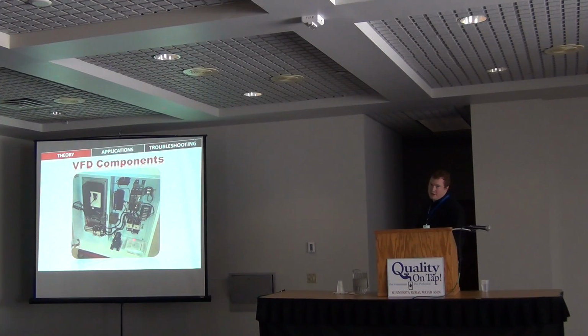This is either an input line reactor, which is a device that's used to oppose rapid changes in current, so it should protect your VFD and reduce harmonics. We'll get into that in a little bit. Or it's an output filter, otherwise known as a dV/dT filter, for if a motor is a long ways away. So I'll talk a little bit more about that a little later in this.